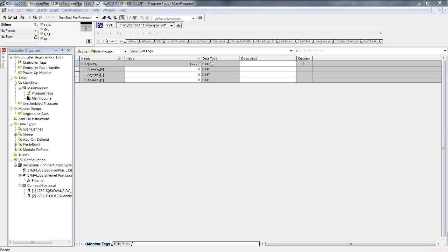When the bits shift left, the most significant bit value moves to the least significant bit position of the next highest double integer in the array. The least significant bit of the lowest double integer sucks in a 0 or 1 from the source bit. And the most significant bit of the highest double integer pops its value out to wherever it came from. We say bit space.